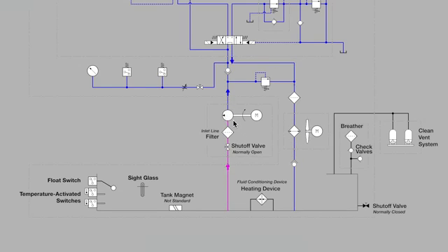And then we see a circle symbol with a single triangle pointing outward, and this indicates the pump. And in this case, it's a very simple pump. It's a fixed displacement pump. No controls associated with this pump when we see only that very simple circle. The double parallel line indicates a mechanical connection of some sort, and in this case, it is the shaft from our electric motor to the pump.